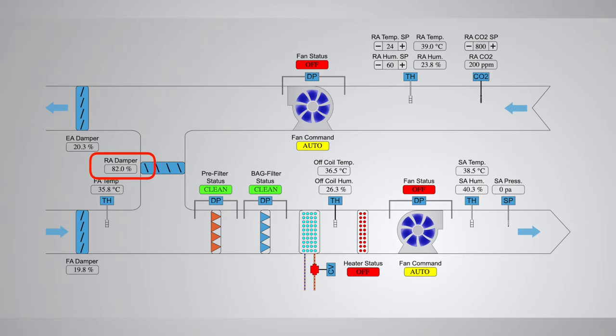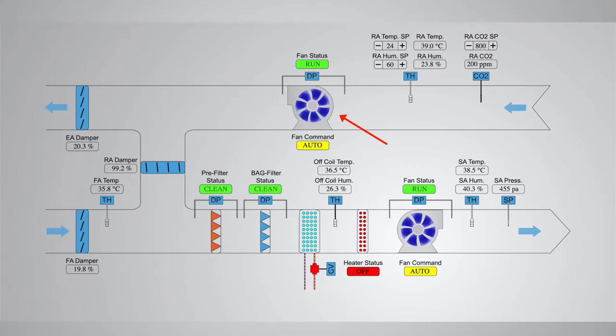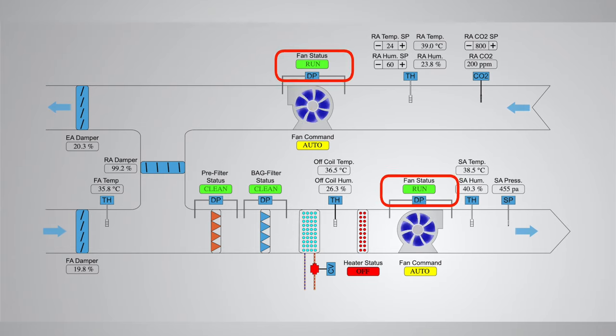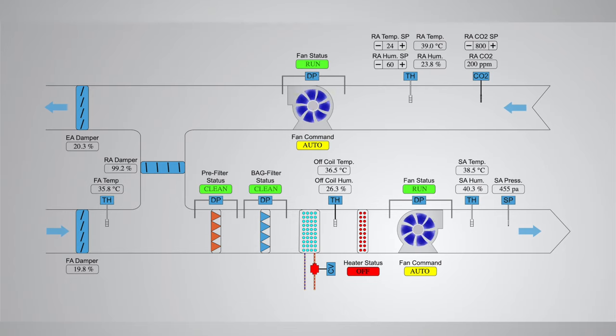This allows the AHU to utilize the already cooled return air to be recirculated to the space, thus reducing the use of chilled water. When the return air damper open position feedback is above a predefined limit of 95%, the BMS will issue a start command to the supply fan, and the return fan is started after a short time delay. The fan run status will be determined by the air differential pressure switch installed across the fan. After confirmation of both fans' run status, the BMS will enable the priority control loop, which is the temperature control loop, by opening the chilled water control valve.